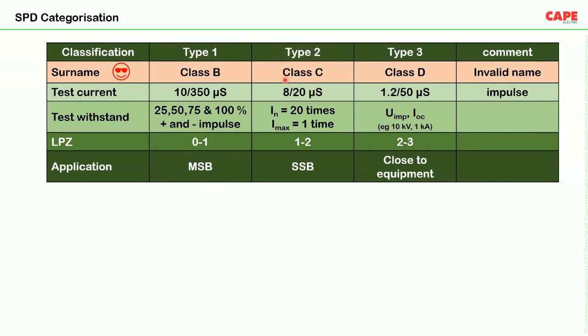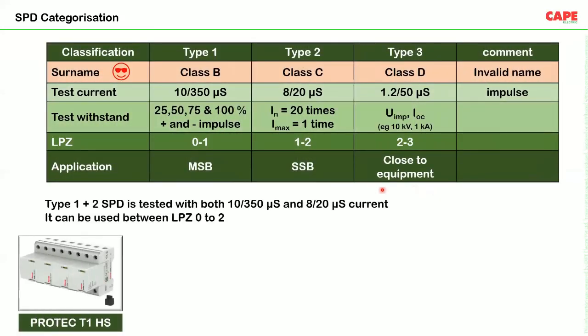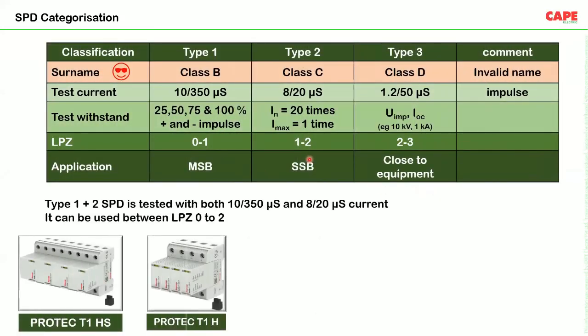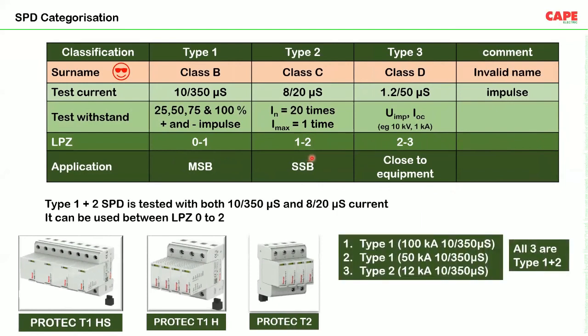The second type of SPD is type 2 SPD, which is tested for 8 by 20 microseconds. These devices are tested for nominal discharge current 20 times and maximum discharge current 1 time. The application is between lightning protection zone 1 to 2, in the sub switchboard. Type 3 devices are closer to your equipment.